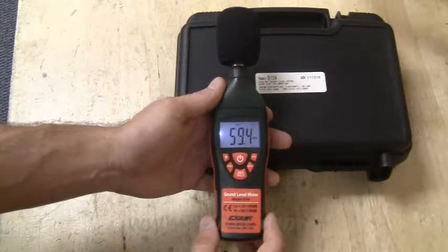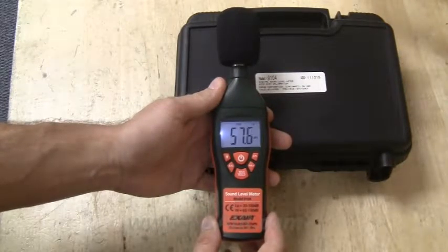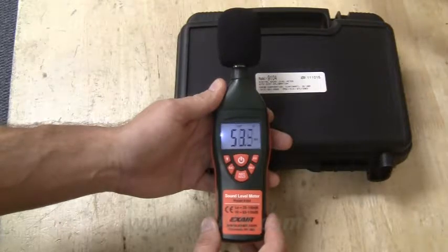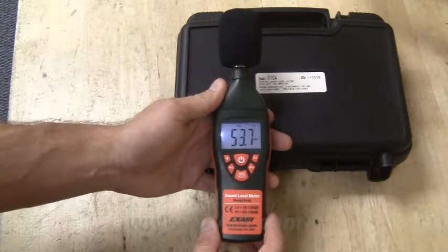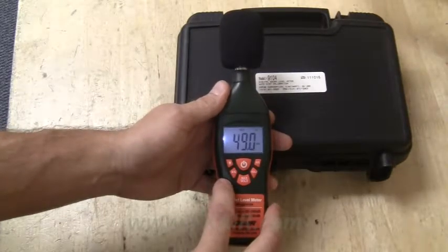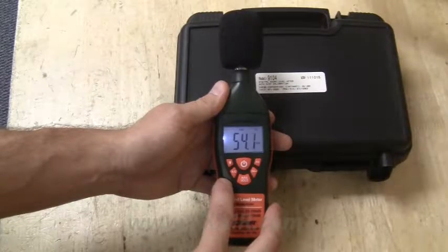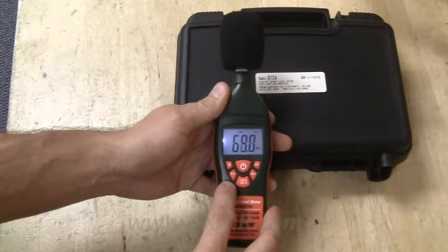The EXAIR 9104 Digital Sound Level Meter measures and displays sound pressure levels in decibels from 35 to 130 dB. The LCD can be backlit for viewing readings in dimly lit areas, with several user-selectable features such as frequency weighting between A and C. DBA is similar to the response of a human ear and suitable for OSHA regulatory purposes, while DBC is suitable for measuring machine noise.